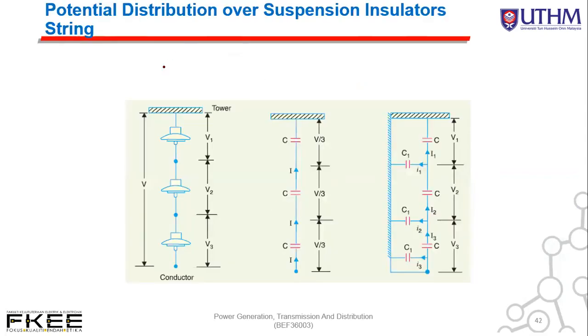Potential distribution over a suspension insulator string: for a suspension insulator with discs stacked in series — for example, three discs with voltages V1, V2, and V3 — V3 (nearest to the conductor) should be the highest. In circuit form, each disc can be represented as a capacitor C for three sections. If voltages were equal, each would be V/3. There is also shunt capacitance between the insulator metalwork and the tower.